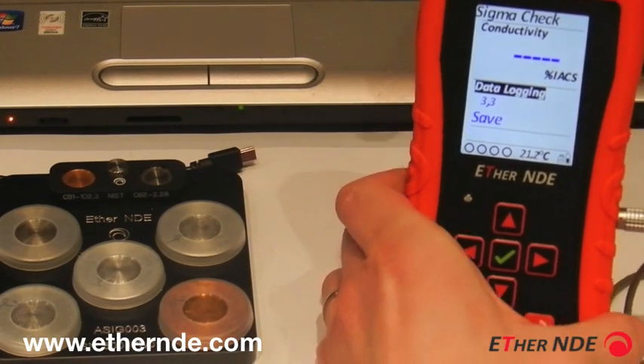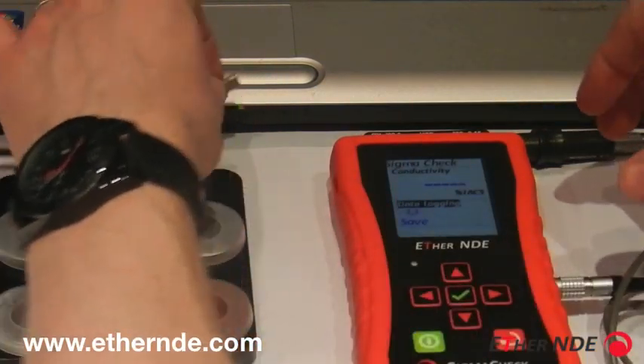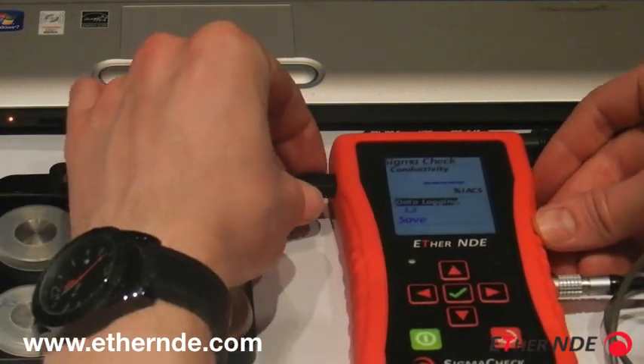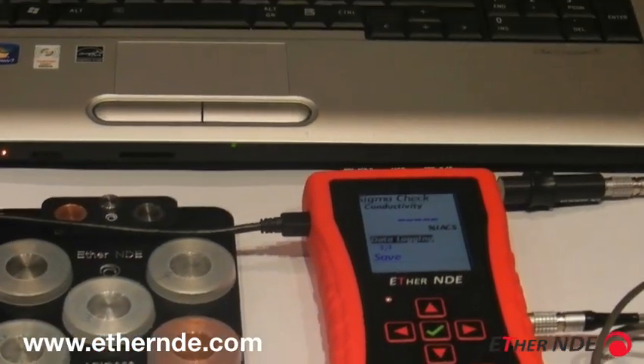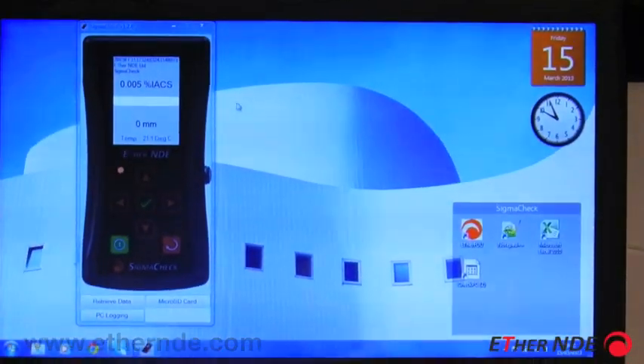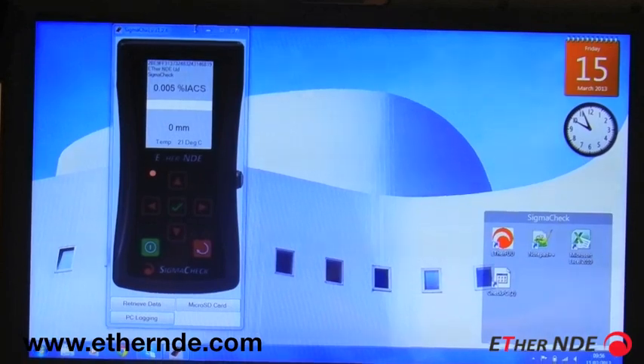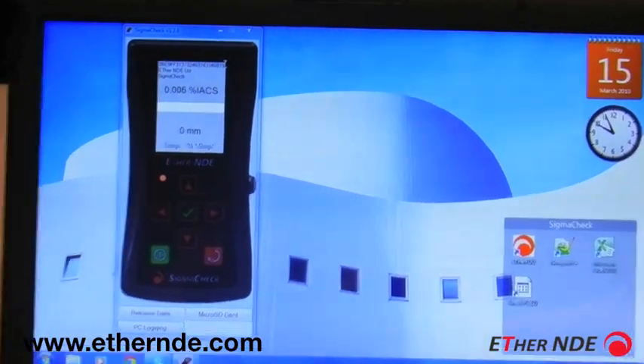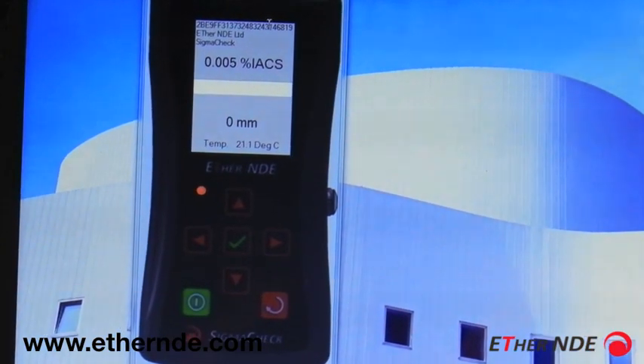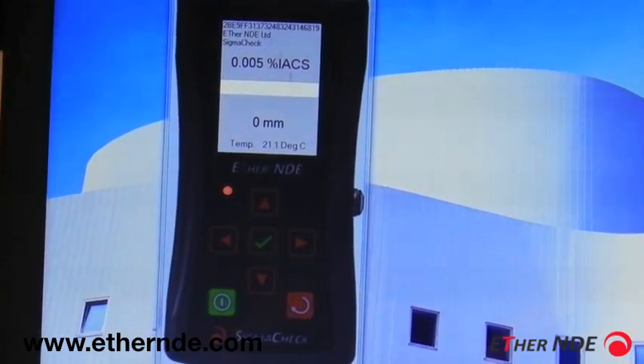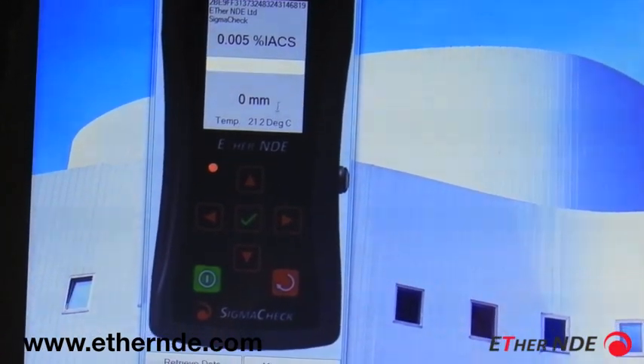What I should do now is analyze the data on a PC. So I shall connect the SigmaCheck with this USB cable to the PC. Now if we go to the PC, here I'm running SigmaCheck PC — it's a host PC package that will connect to the SigmaCheck. It indicates the ID of the instrument, the fact we have a SigmaCheck connected, and it displays live conductivity, lift-off, and temperature information.